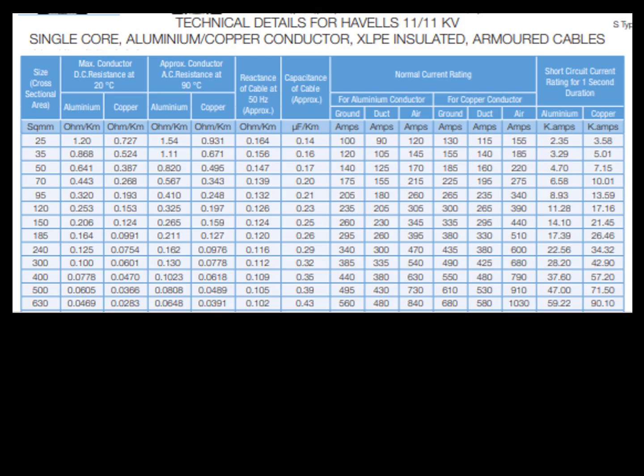Friends, in the previous slide, we have seen the physical properties of the cables. In this particular slide, we are seeing technical details for 11 kV single core aluminum or copper conductor XLPE insulated armored cables. The first column gives the sizes, and you can see the normal current rating for aluminum and copper in three different situations: ground, duct, and air. These are nominal current ratings we can take care of. Similarly, short circuit capacities.